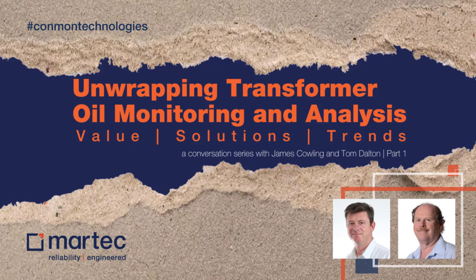From a Martec offering point of view, Martec are effectively a condition monitoring company that are able to supply portable dissolved gas analyzers and moisture analyzers, which are effectively units that you can take to site. You can pull a sample on the transformer in the field and you can analyze it and determine what's wrong with the transformer within around about an hour.